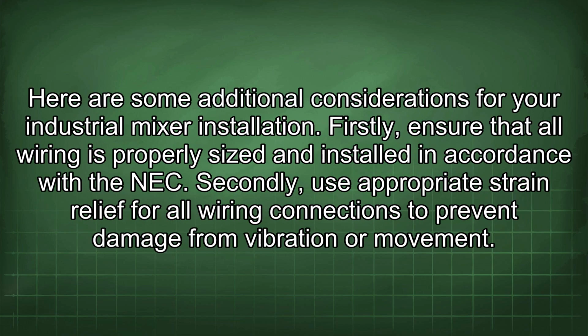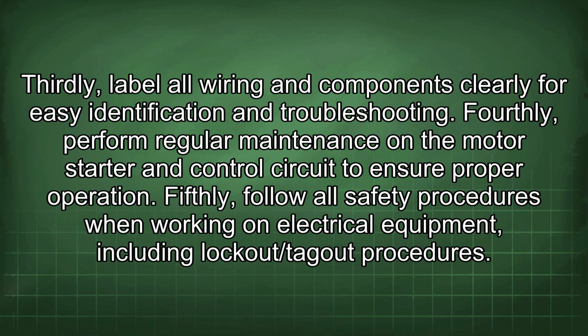Here are some additional considerations for your industrial mixer installation. Firstly, ensure that all wiring is properly sized and installed in accordance with the NEC. Secondly, use appropriate strain relief for all wiring connections to prevent damage from vibration or movement. Thirdly, label all wiring and components clearly for easy identification and troubleshooting. Fourthly, perform regular maintenance on the motor starter and control circuit to ensure proper operation. Fifthly, follow all safety procedures when working on electrical equipment, including lockout/tagout procedures.